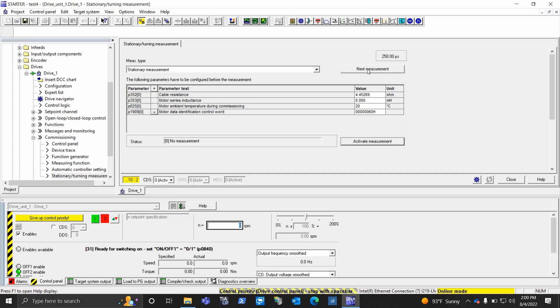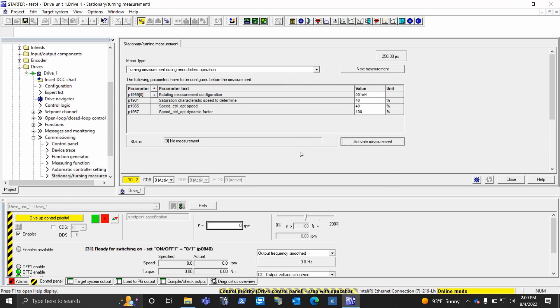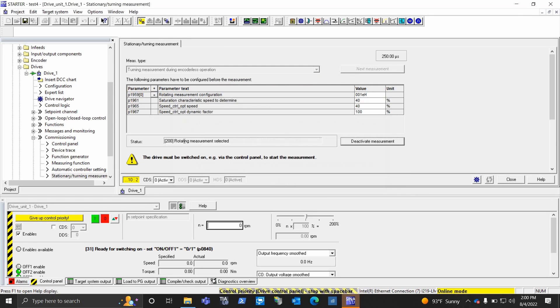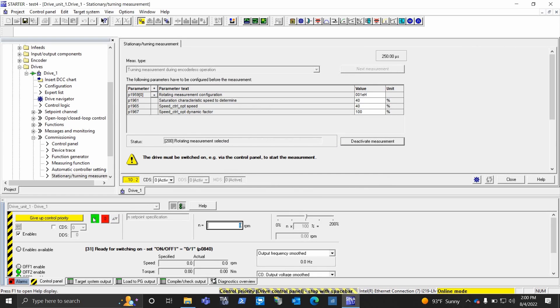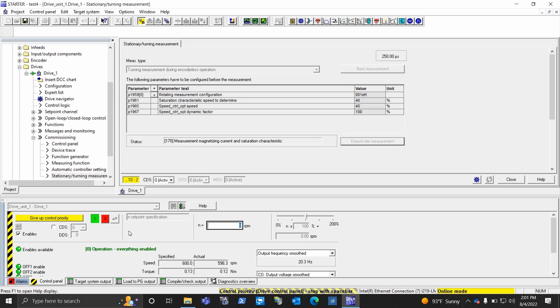We're going to go to the next. So we're in encoderless operation, so I want to do this tune. Now I've activated it, it's ready to go. You have to hit start again. Once again, it will start telling you the details of what's happening. You can see from the speed it's actually spinning the motor and running through its tuning characteristics. Now if this had an encoder, there's a fourth tune that you go up there and hit next and select, but this is the last tune for open loop vector motors.